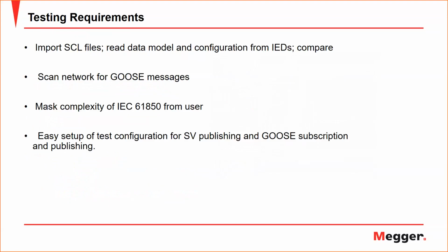So testing requirements, this is a few things that I would mention very quickly. You need a way to import SCL files. SCL files are substation configuration language files that have all the information about your substation, all the communication mappings, all the capabilities of your IEDs, all the description for them, and be able to do comparison for these SCL files and what you have in your network, and also able to copy the information from these files to your test equipment for the specific device that you are planning to test. And also for the comparison, you need the ability to scan the network to see that what you have in your network is exactly what you have in your files to start doing the test.